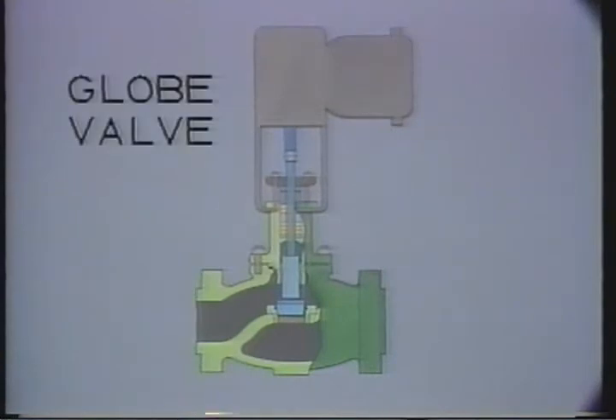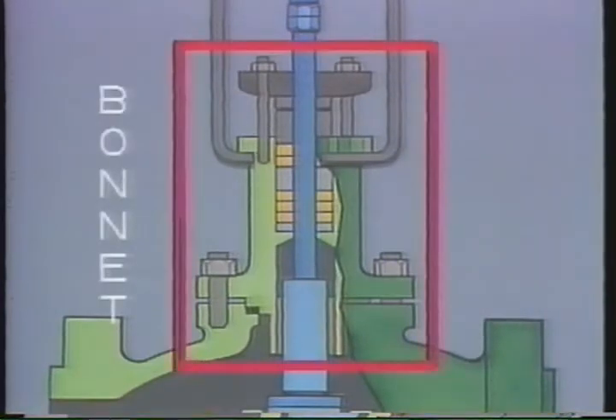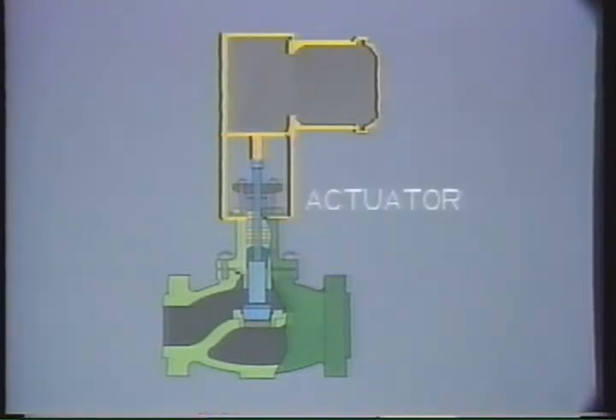Globe valves get their name from the globular shape of their bodies. This valve connects to the process piping and serves as the main casing for the internal parts of the device. This valve has a bonnet connected to the valve body. The bonnet contains the stem seal or packing assembly. In between the body and bonnet, there's usually a gasket to seal the connection between the two parts. The actuator responds to the signals from the controller to initiate movement of the parts inside the valve.